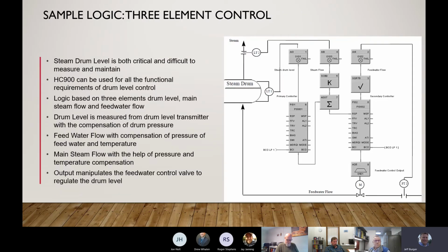We were talking about the three-element control. As you can see on the far right-hand side, this is a control architecture, the function block architecture that you would have in the HC900, that would allow you to build a 3-element control system. And as you can see, around this function block is a description of the final control elements and the sensors that you would have leading into that application. So you would have your level, your steam drum level, feed water that goes into that drum. You might have a motor or a valve down here that you're controlling. You might have a flow transmitter here that's feeding that flow of that feed water back into your control system.